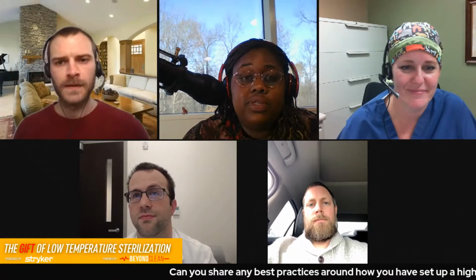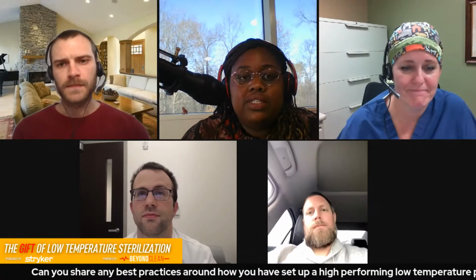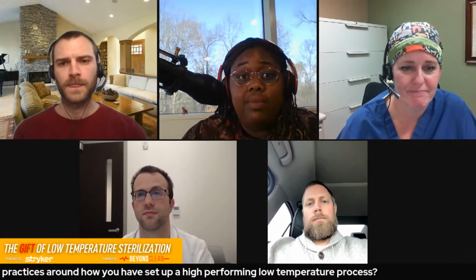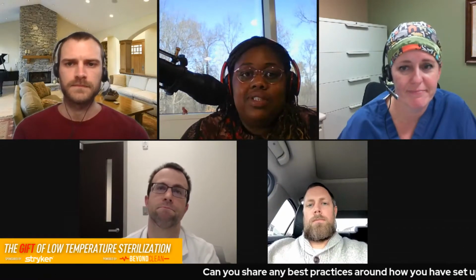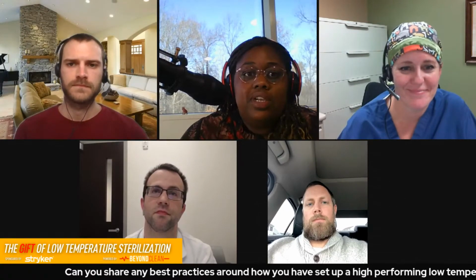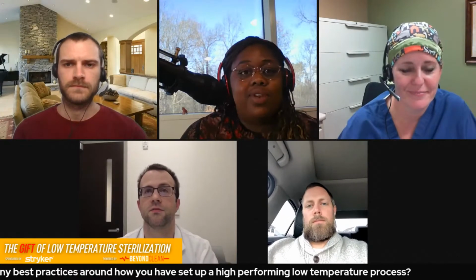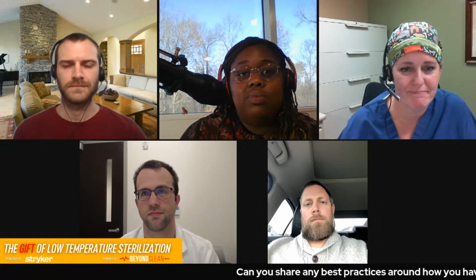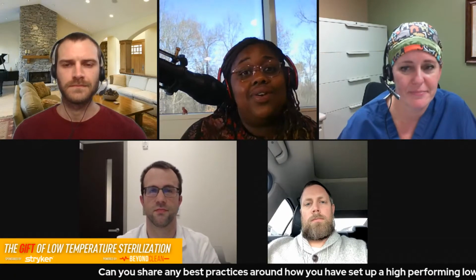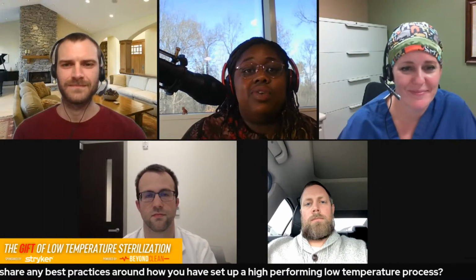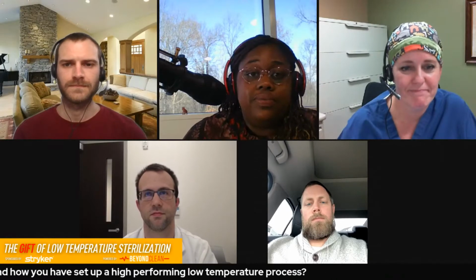Absolutely. One of the low-hanging fruit, I think, is the frequency with which we train. Oftentimes in sterile processing, we may only educate when the thing is new, right? When the machine gets installed, or when we add a new cycle, or we buy a new piece of equipment. Because these are foundational skills that we want staff to be competent on, it's not acceptable to do just a yearly competency. You want a process in place where, whether it's monthly, bi-monthly, however you want to do it, you're coming back to these basic concepts and catching that drift. This is how we eliminate staff running things on the wrong cycle, or using the wrong processes, or not using their gloves even though they know they're supposed to. Having these consistent reminders about foundational skills is really, really critical.